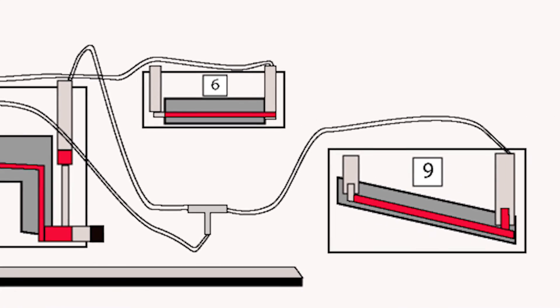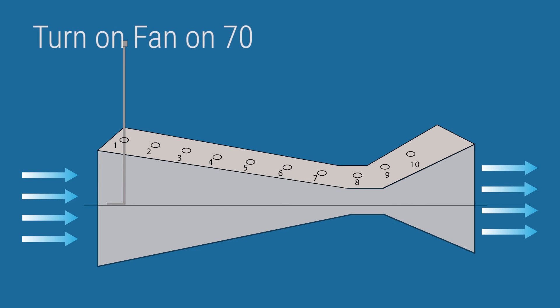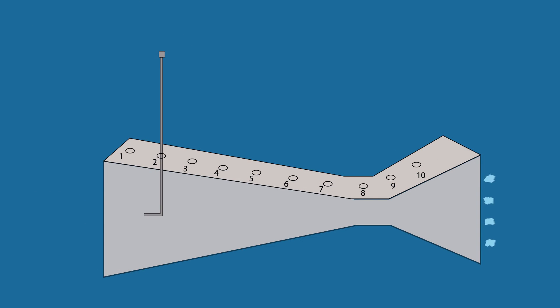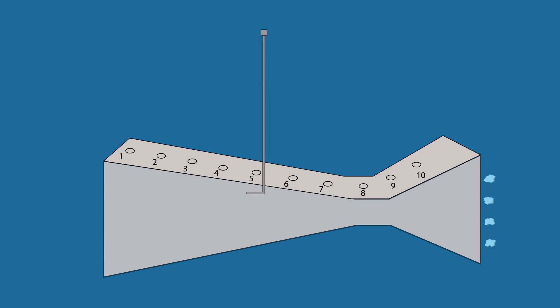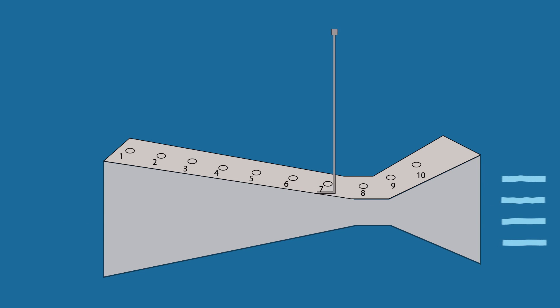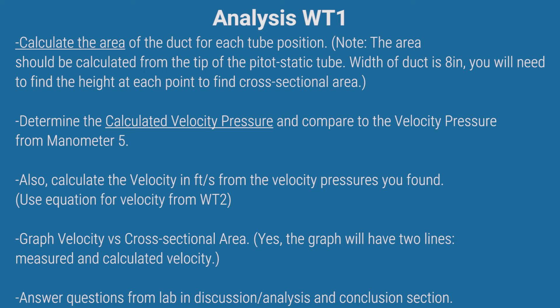For manometers 6 and 9, we're only connecting to the lower side. Turn on the fan to 70. Place the pitot tube to hole 1 and adjust it so the tip is centered. After recording the pressure, repeat the step through holes 2 through 10. You also need to find the calculated velocity pressure by subtracting the static pressure reading from the total pressure reading. This value must be close to the velocity pressure obtained from manometer 5.